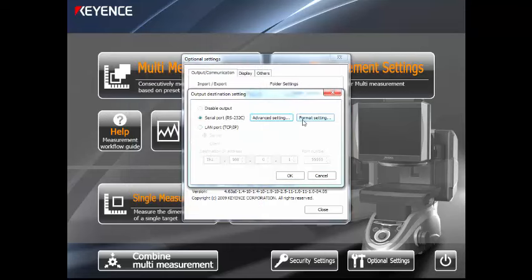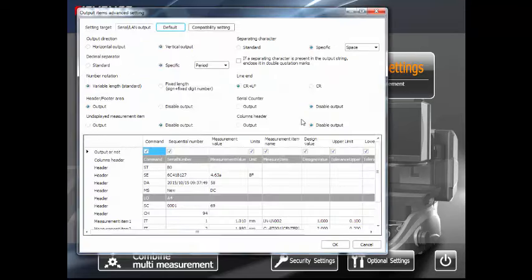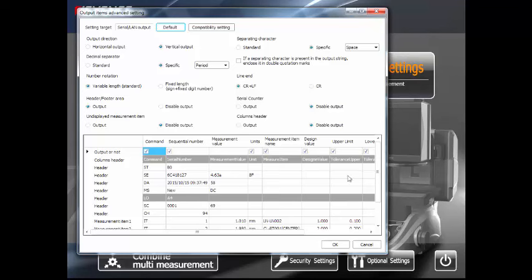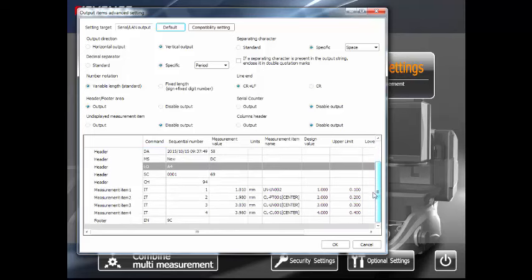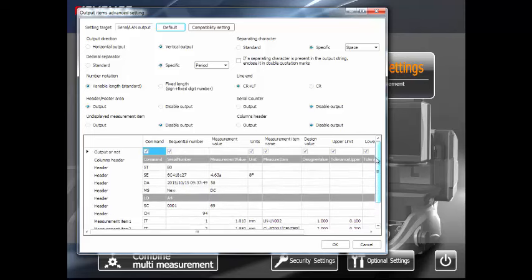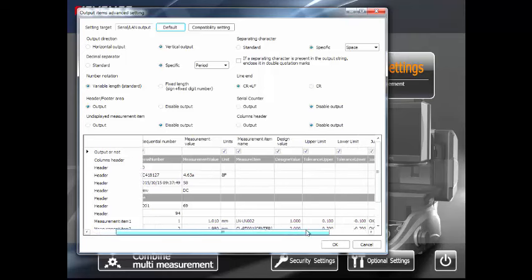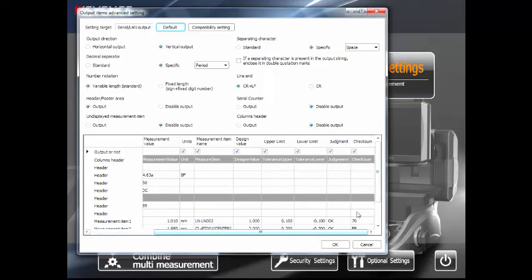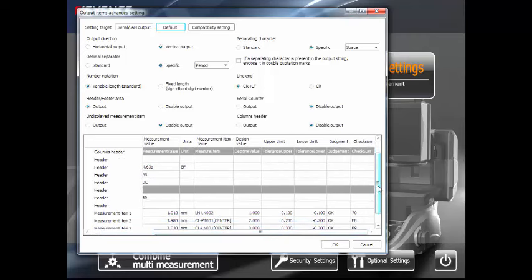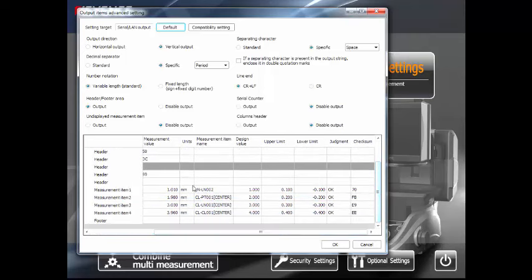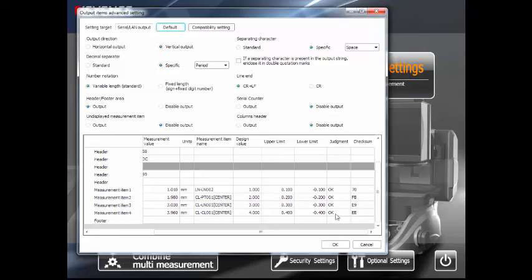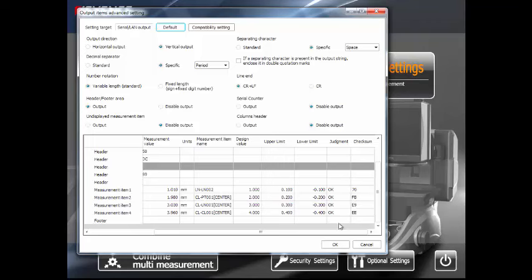You can also hit Format Setting here. This gives you the ability to change what information is going to be outputted in that RS-232. Here you can take a look at the format and see exactly everything that's coming out. Your actual measured values are going to be right over here. Your names, design values, upper-lower spec limits, judgment values are right here. If you're looking for OKs, no goods, that sort of thing. Checksums are for RS-232 equipment that needs to make sure it got all the information.